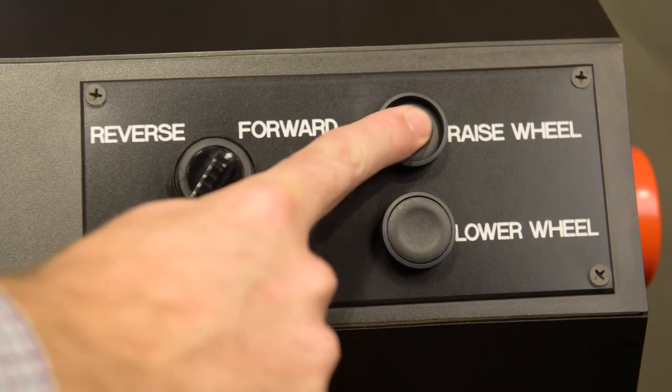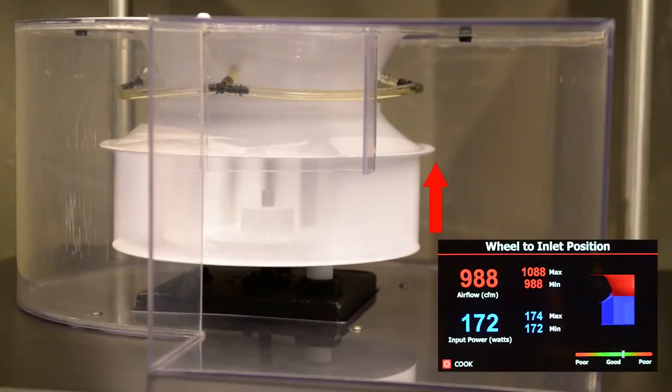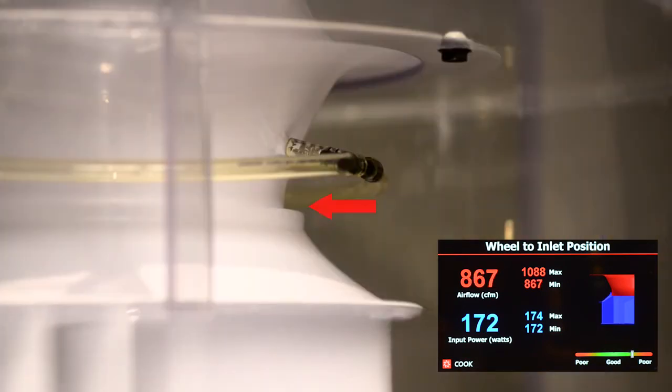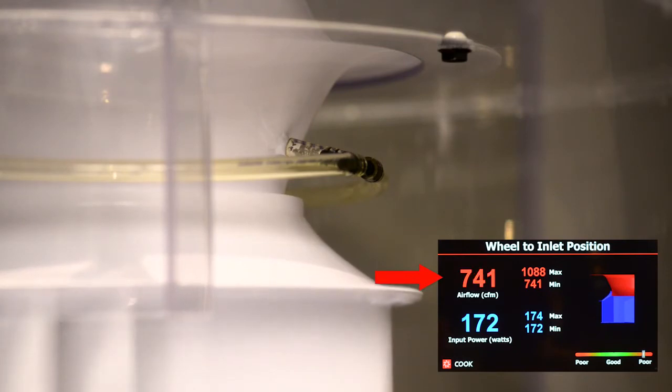First, we'll raise the wheel to increase the overlap and see what happens. Increasing the overlap makes the gap between the wheel and inlet smaller. You can see that the airflow is dropping as the wheel gets higher.